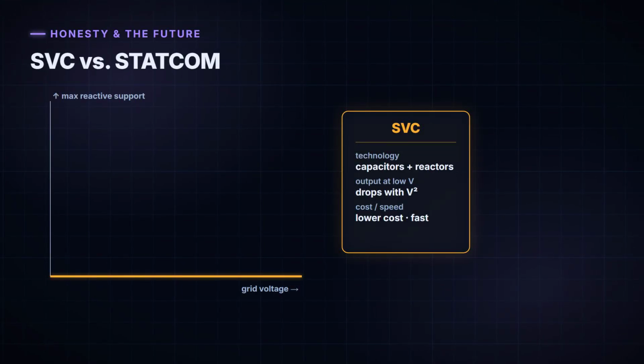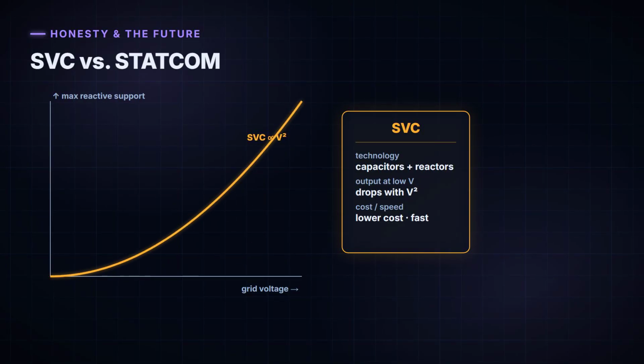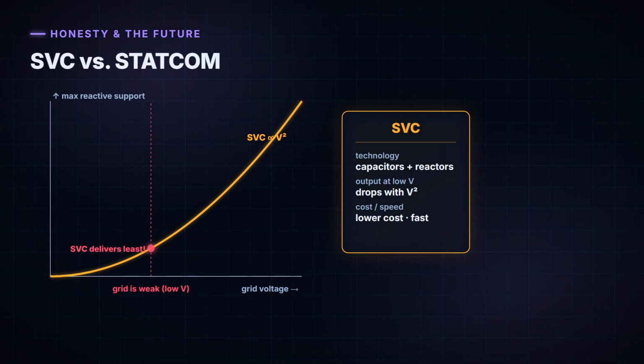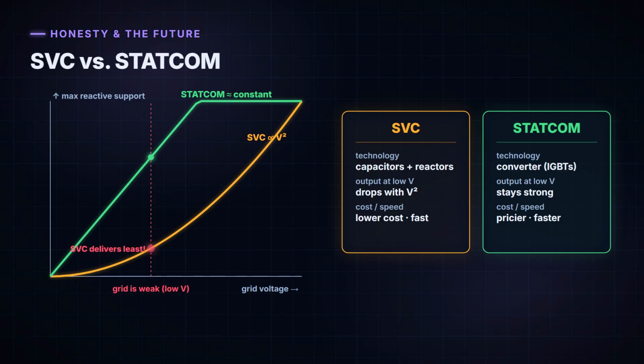Now, in the spirit of honesty, let's talk about the SVC's main limitation, because it points directly at the future. The SVC is built from capacitors and reactors, and the reactive power a capacitor can deliver depends on the voltage squared. So just when the grid voltage sags badly and you need the most support, the SVC can deliver the least. That weakness led to its successor, the STATCOM, which uses more advanced converters to deliver steady reactive power even when the voltage is low. They're cousins, solving the same problem with different technology, and engineers choose between them based on cost, response speed, and how weak the grid is.